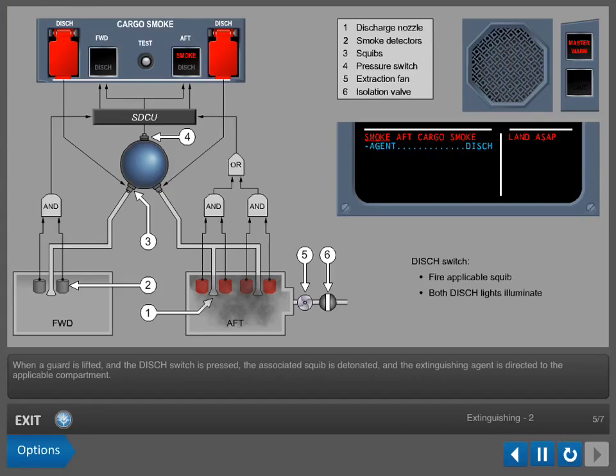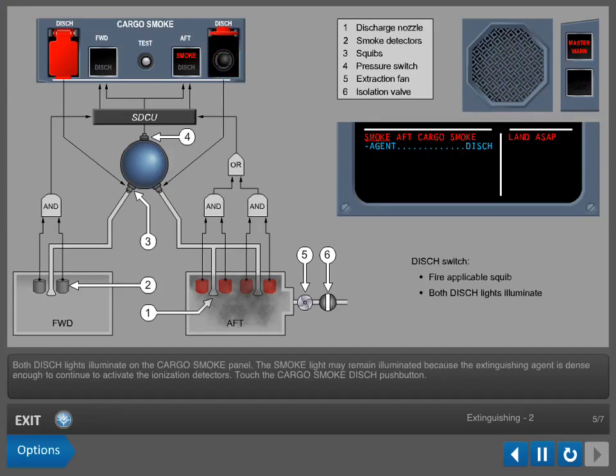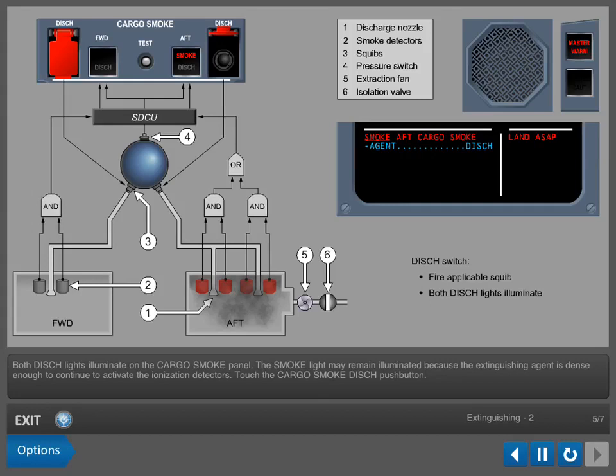When a guard is lifted and the discharge switch is pressed, the associated squib is detonated and the extinguishing agent is directed to the applicable compartment. Both discharge lights illuminate on the cargo smoke panel. The smoke light may remain illuminated because the extinguishing agent is dense enough to continue to activate the ionization detectors.